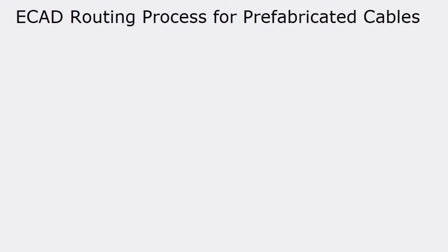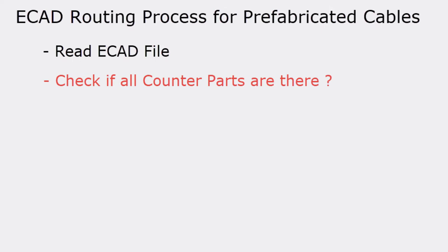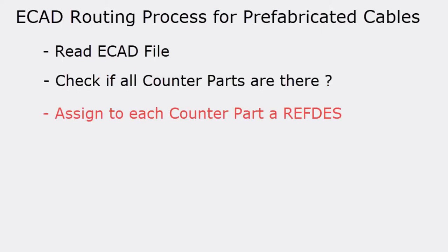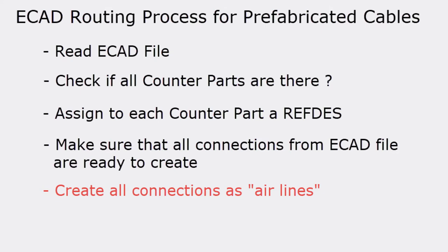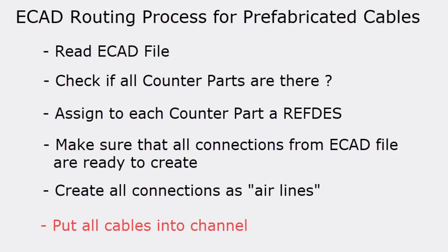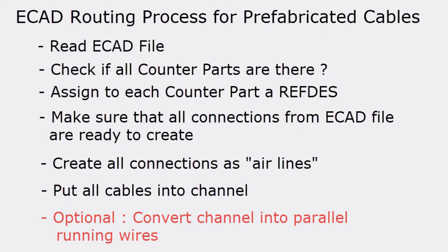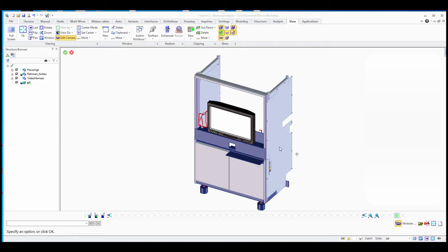The process for prefabricated cable ECAD routing is: first, read the ECAD file where all connections are defined; then check that all counterparts in the ECAD file are available in the model; assign reference designators so we know which endpoint connects where; verify all connections are valid; create them all as air lines; and finally route all cables automatically to the channel. Optionally, you can convert the channel into parallel running wires.